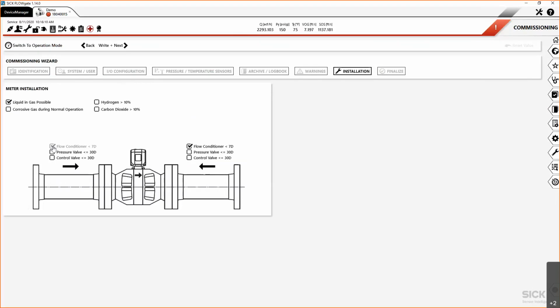In other words, do I have a flow conditioner upstream of the meter? Do I have two flow conditioners, one upstream and one downstream, because this is a bidirectional installation? Do I have a pressure regulator or control valve up or downstream of the meter? Is this meter located downstream of a separator or some kind of dehy unit where I might possibly have liquid present inside the meter if those fail? So this is how you set up the meter.